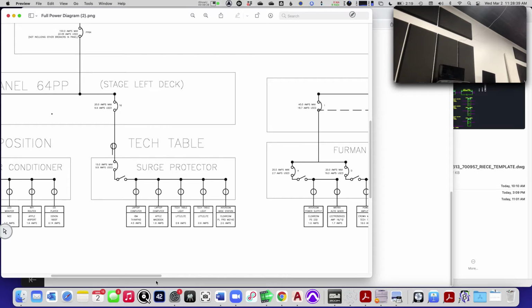Yes. Well, presumably this would trip first. Would it trip the other one? No. If this breaker does its job, it'll trip before this one has a chance to. Okay? And that's, again, to keep this from shutting down everything else that's plugged into that circuit. Right? Because you could have 3 surge protectors on that circuit, because there could be 3 different receptacles around the room that all feed off that circuit. And so if the breaker on the surge protector has a smaller breaking capacity than the breaker in the panel, then presumably that will trip before the one in the wall trips and shuts the whole room down, right?